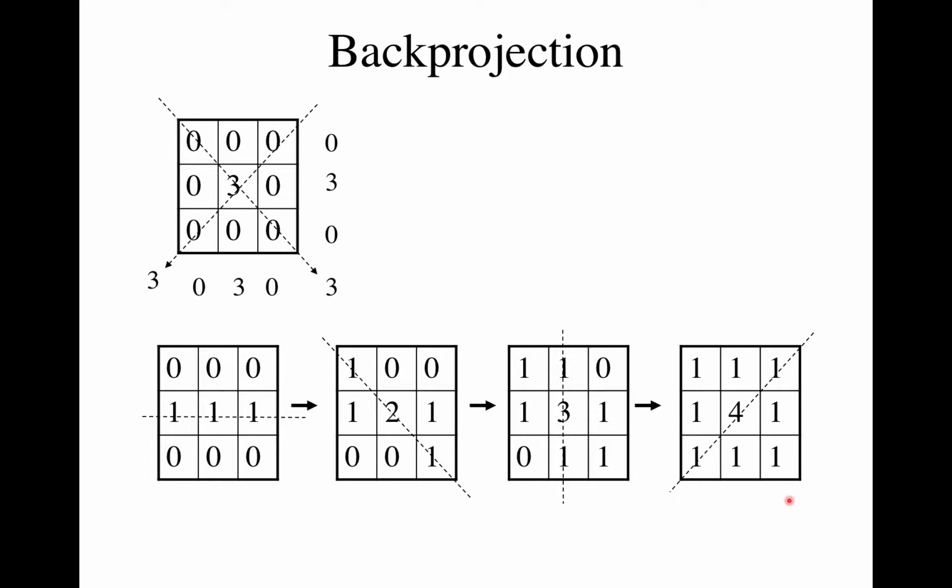And it's not a bad picture when you think about it, right? It's pretty darn good, right? If you took the baseline off, you'd get the actual answer. So this is naive back projection, and that's what was done in the early days of clinical CT, and it's still done to this day. After we'll see there's some modifications you do to it, because it can be done very quickly, right? You don't have to invert a huge matrix of equations. You just back project this data and paint a picture, essentially.